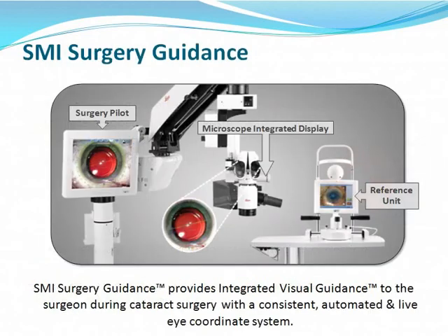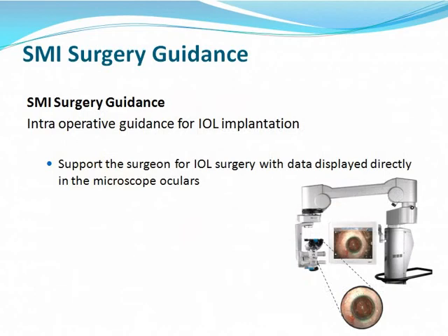Here you have a setup of the SMI surgery guidance system, where you have the reference unit that measures the astigmatism before surgery using typical landmarks of the eye in terms of iris features and limbal vessels. This is then loaded into the surgery pilot, and through the microscope-integrated display, the surgeon gets this view in the microscope oculars. The idea of SMI surgery guidance is that it helps the surgeon with guidance for intraocular lens implantation in terms of centration of lenses, multifocal lenses, and alignment of toric intraocular lenses.